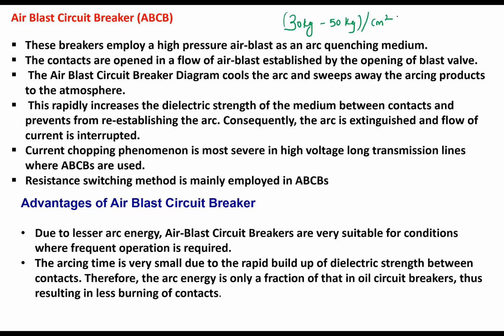The breakers employ high pressure air blast as an arc quenching medium. The contacts are opened in the flow of air blast established by opening blast valves. So what happens? There will be a reservoir. Reservoir means nothing but a tank in which high pressure air is stored. A pipeline carrying this high pressure air is connected to the chamber where the fixed and moving contacts are present.